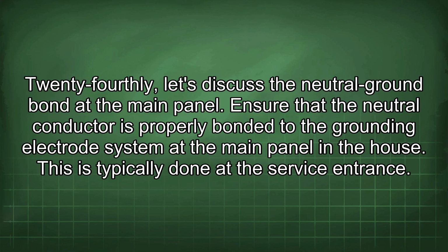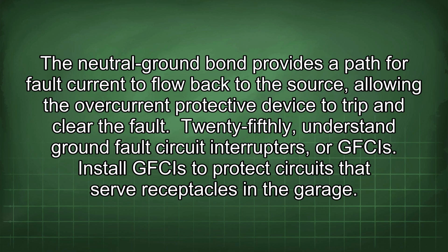24thly, let's discuss the neutral ground bond at the main panel. Ensure that the neutral conductor is properly bonded to the grounding electrode system at the main panel in the house. This is typically done at the service entrance. The neutral ground bond provides a path for fault current to flow back to the source, allowing the overcurrent protective device to trip and clear the fault.